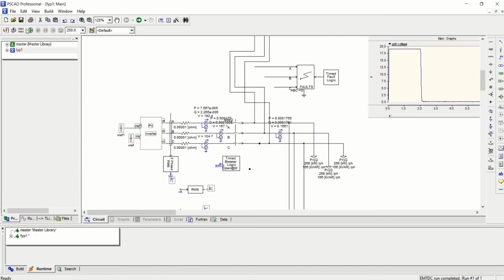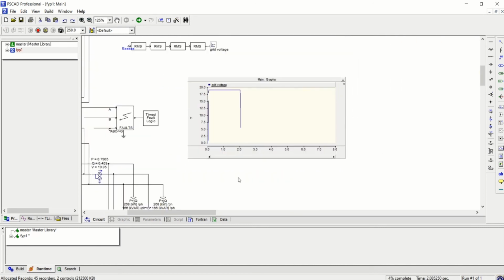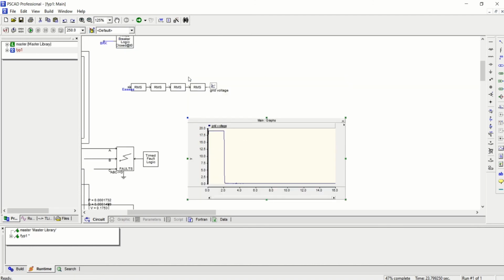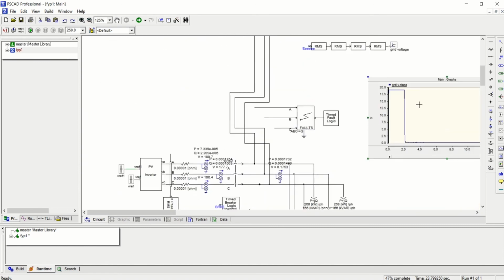Then let's run the simulation. You can see here the voltage drop in islanding mode. Let's look at the value of the voltage drop. It drops from 19 kilovolts to nearly 0.1, 0.2. So my system network is considered to be in islanding mode because of the voltage drop right here.